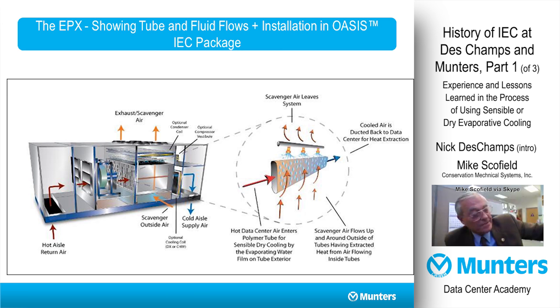The reduction in the performance, the reduction in energy requirements are tremendous because this heat rejection is accomplished roughly at 0.2 kW per ton or less. And comparing that to an air-cooled water chiller or an air-cooled DX system, where the heat is extracted and then through refrigeration rejected to the atmosphere, the kW per ton is usually around 1 or 1.2. So tremendous increase in energy efficiency of these systems in data center applications.